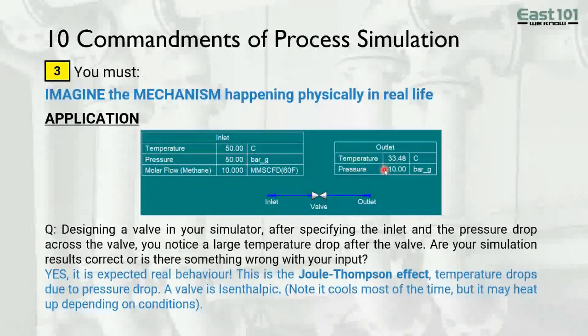So obviously what's going on here is the Joule-Thomson effect being calculated by the simulator. Should you be surprised? Well, no, obviously, because when you see this pressure drop, the first thing that should come to mind is it's a valve, an expansion, a Joule-Thomson effect, and you should expect a temperature drop.